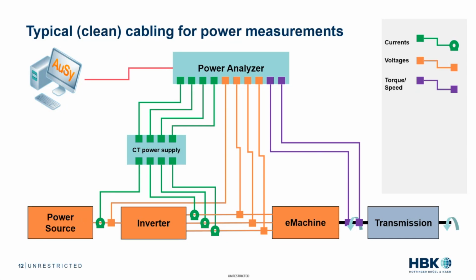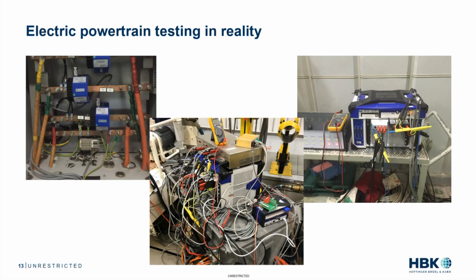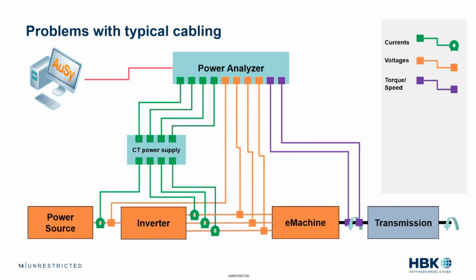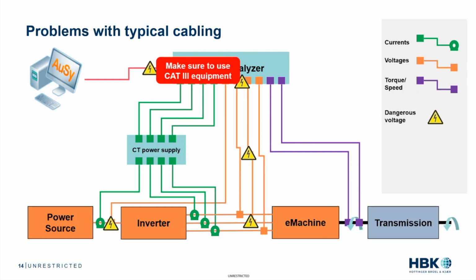But we need to deal with reality here, and that's why we're all here, to see how to mitigate the issues of the real world. So maybe you've set up some of these types of tests and have seen a setup that may look like one of these pictures here, somewhat clean, somewhat very messy. But that's the reality that we're dealing with at times. So basically, what does that lead us to? We've got some dangerous voltages at the power source, and we also have them at the inverter. We also have them in our cables that are going back to the power analyzer or data acquisition system, and even our automated system or dyno. So you want to make sure that you use Cat 3 equipment so that you are very well protected, not only yourself, but also the analyzer and its input.